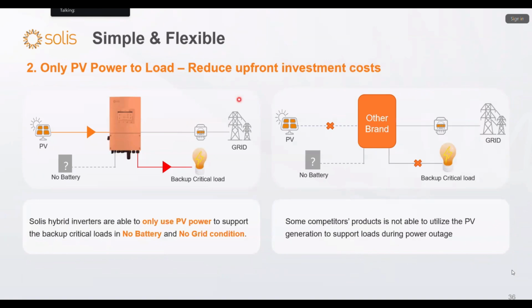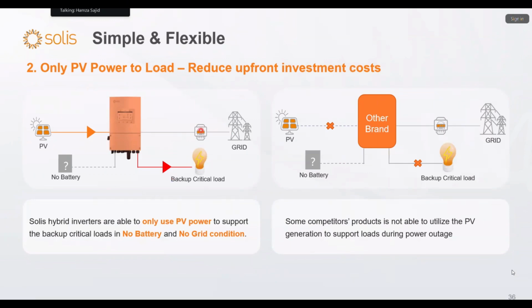In some cases, customers cannot afford the batteries, or they don't want to invest a huge amount in the upfront cost of the batteries. So they can move in a step-by-step system. First, they can install only the PV inverter and the grid system. The Solis inverter can also work with only PV, when the grid is not available and the battery is not available. The inverter can still support directly from PV to the backup port. So all the customers who cannot afford any upfront cost can easily go with the system without any issues for investment. But if you compare with other brands, currently they lack this. If there is no battery, they cannot support the backup.